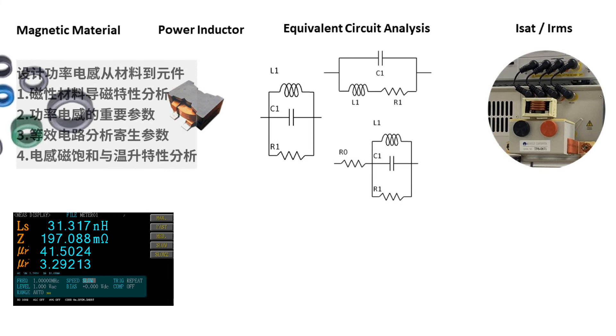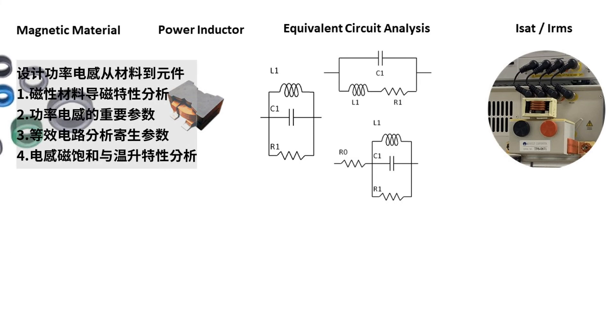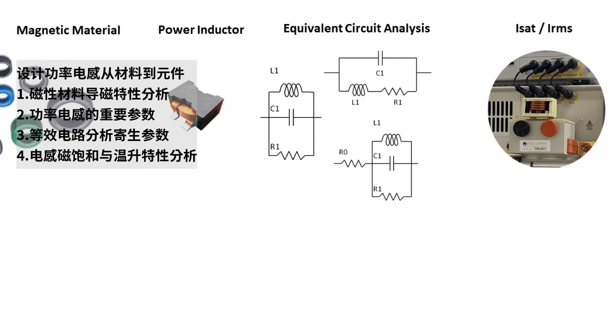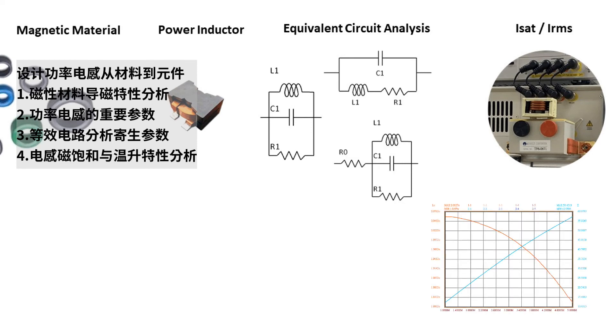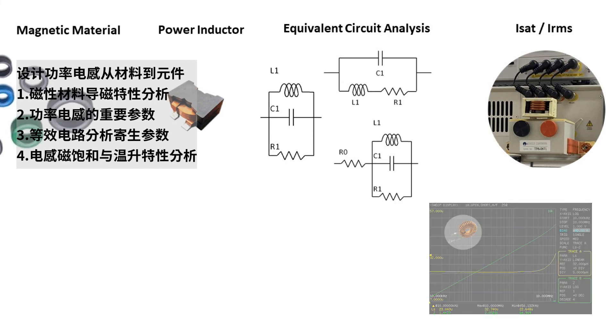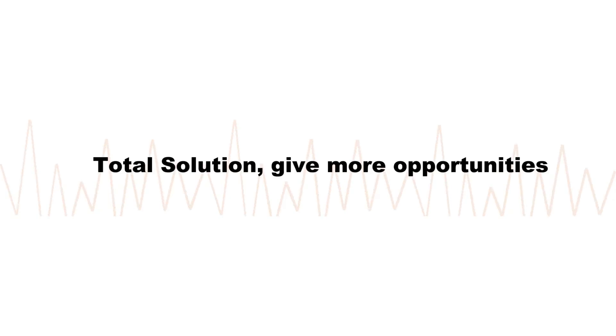The Microtest 6632 features a built-in magnetic permeability function. With its DC bias current source, the maximum current can be as high as 320 amperes at a frequency response of 100 Hz to 10 MHz. It also offers a current graphical display of the magnetic saturation curve.